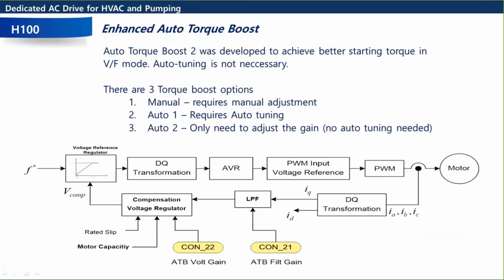If we ever have anybody calling up and they're like, hey, this thing isn't starting up, I need more starting torque, or my voltage is kind of acting funny on the output, usually if we set up automatic torque boost, it just fixes everything most of the time. So there's a manual torque boost, which is what the drive defaults to. And when we're talking about torque boost, we're talking about boosting up the output voltage going to the motor. So when you boost up your output voltage, you should theoretically increase your torque.